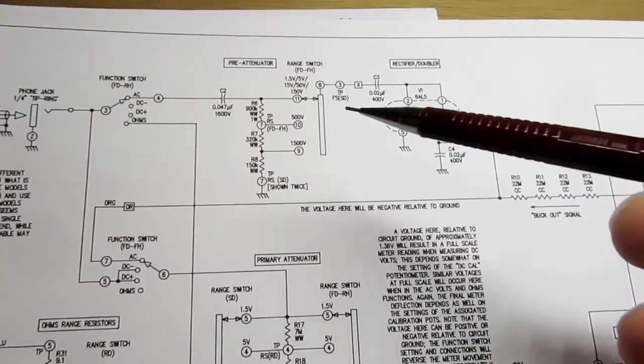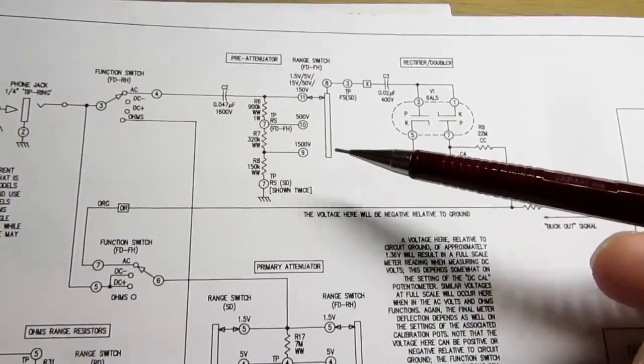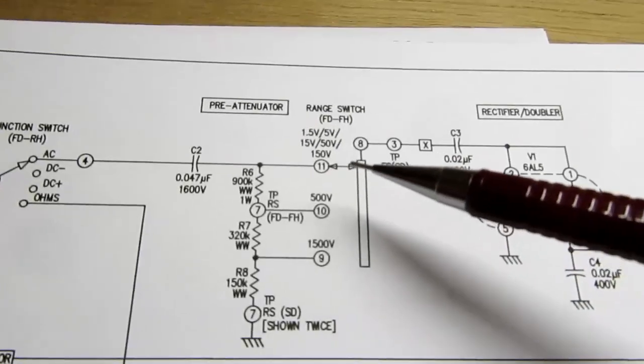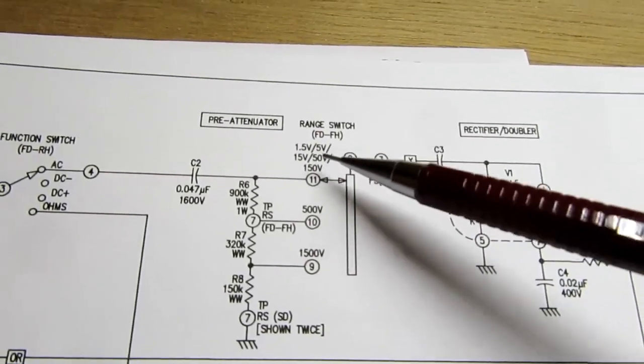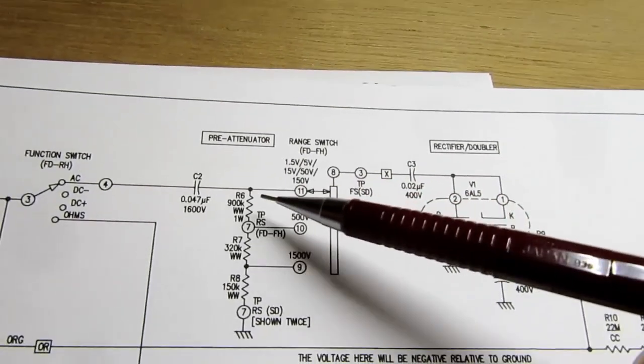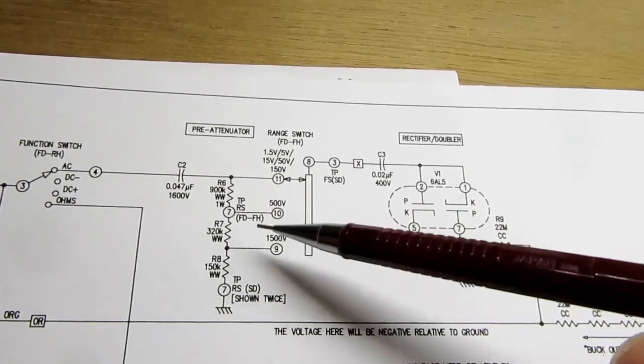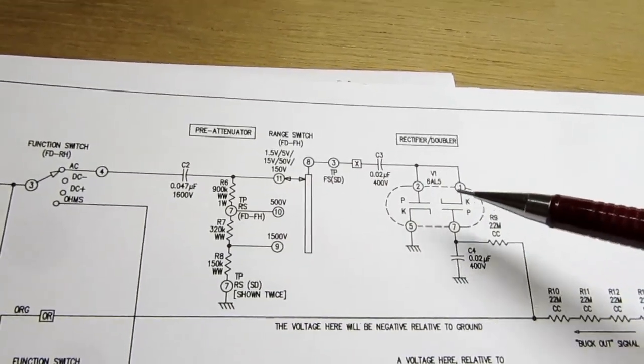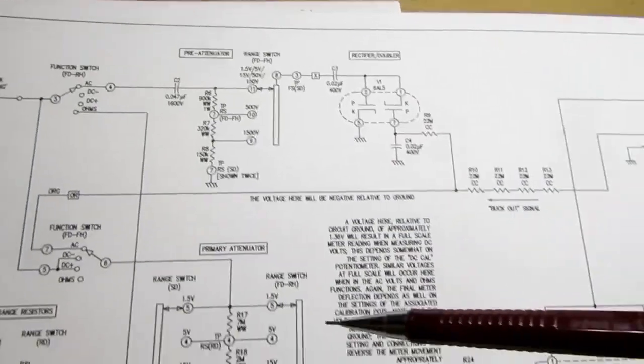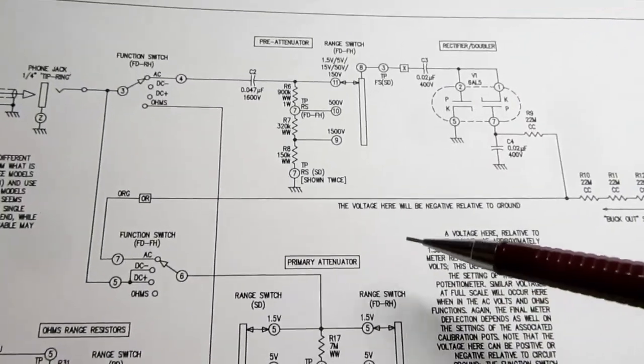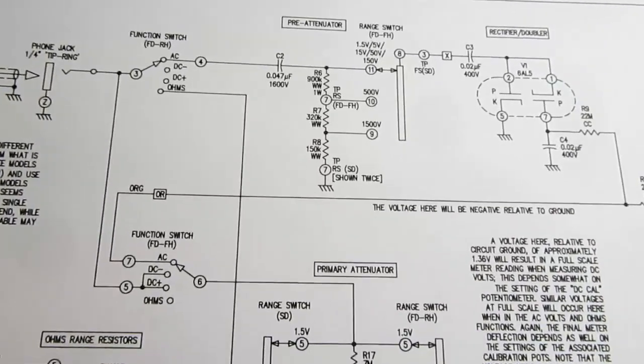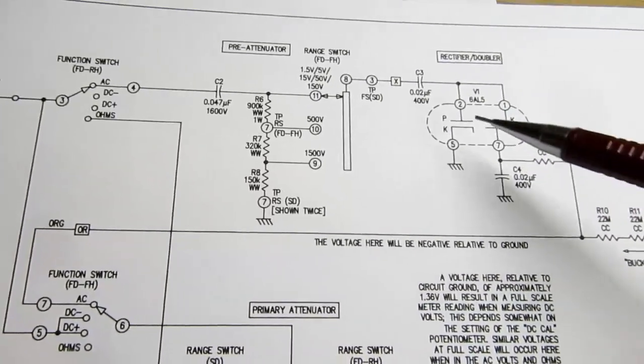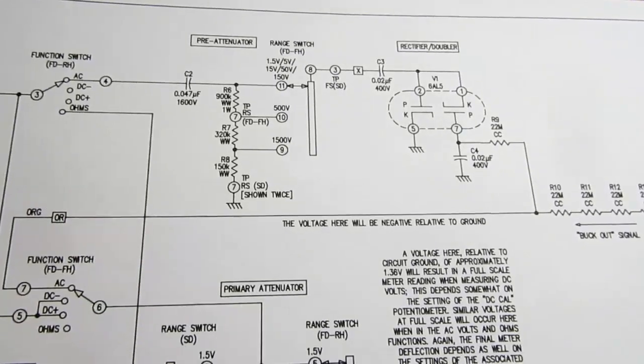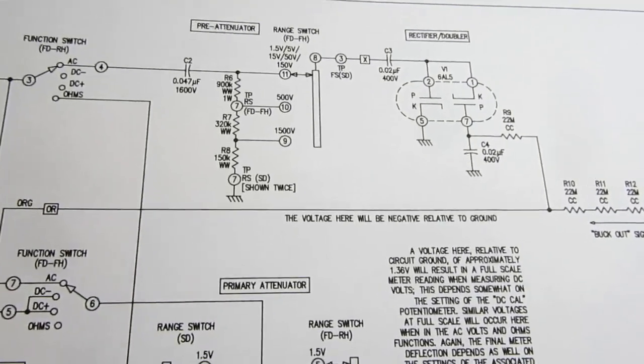Well, why are we doing this pre-attenuator if we're not going to use it? As I mentioned, on almost all the ranges, the 1.5 through the 150 volt range, we don't even use this pre-attenuator. We just sail right on through the rectifier, doubler, and then the primary attenuator and go on to the meter movement. Well, this tube here is only good for voltages up to around 400 volts. That's its maximum.